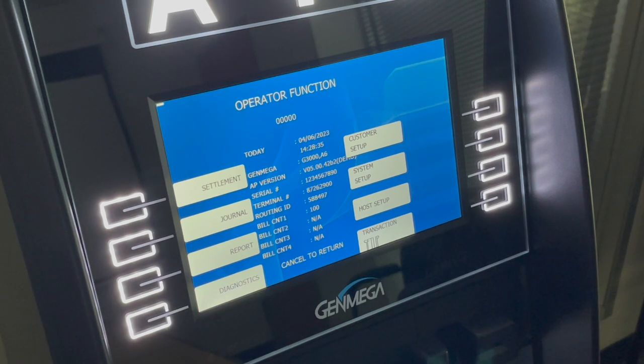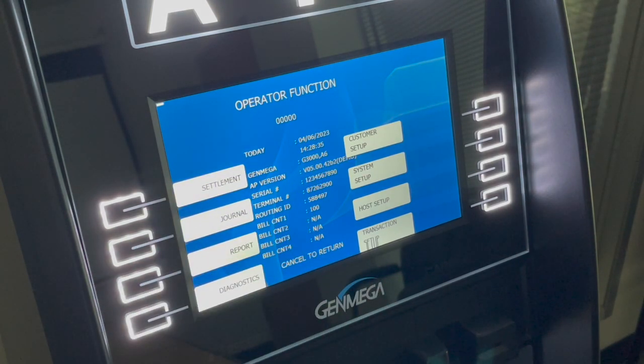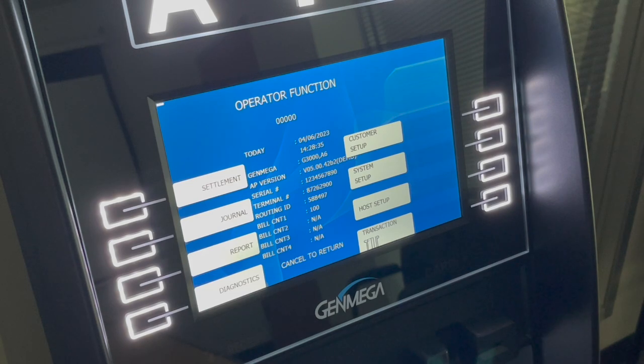Also, if you can see the screen and you can get into the menus, verify that you have the correct software because that also affects the resolution of the screen. In this case, it says G3000 which is appropriate for an ONIX. But if I was to have 2500 software loaded, it would also skew the screen because it's not the same resolution.